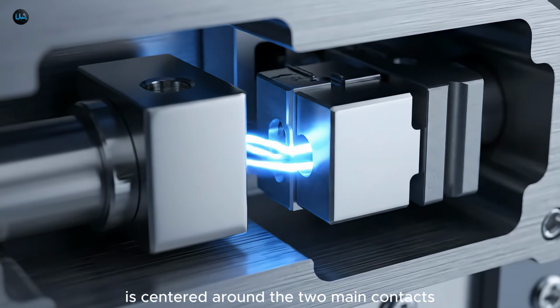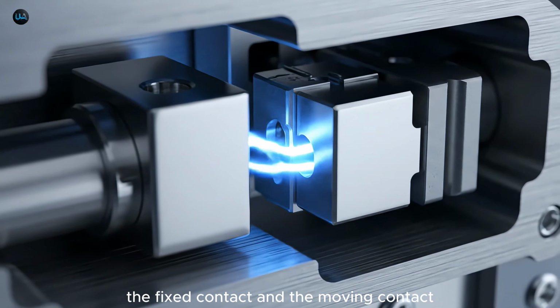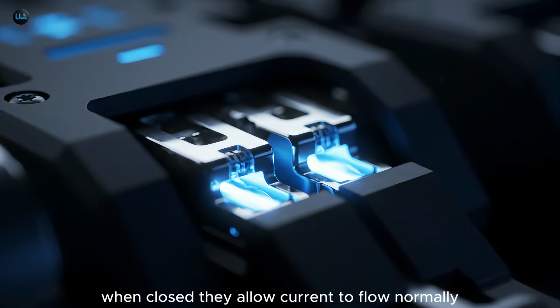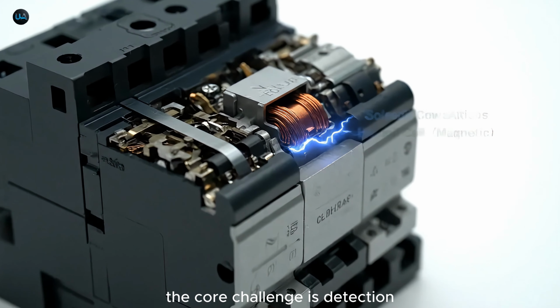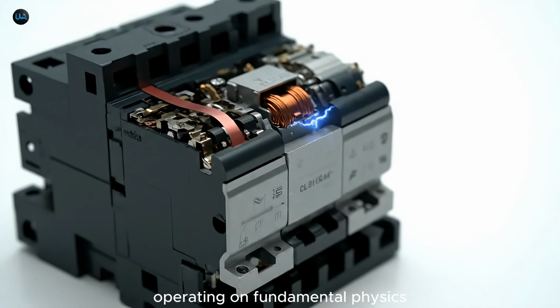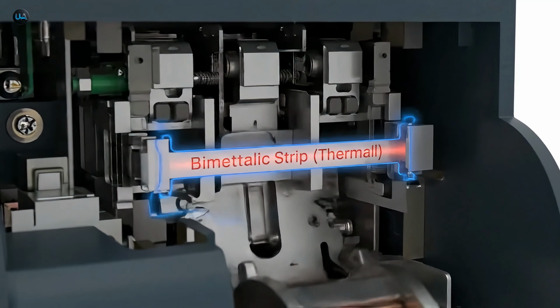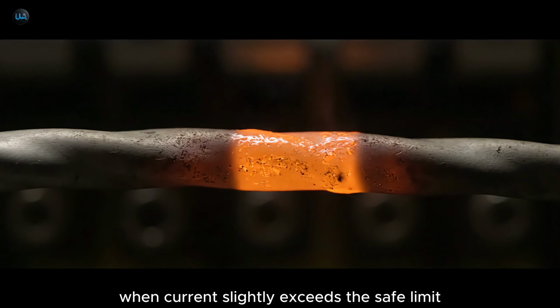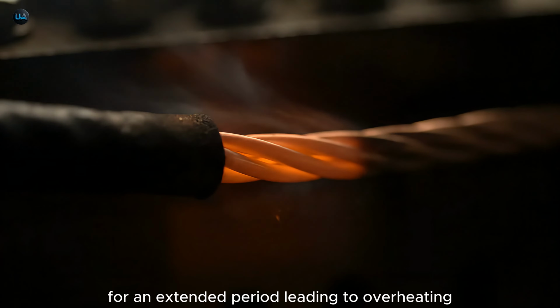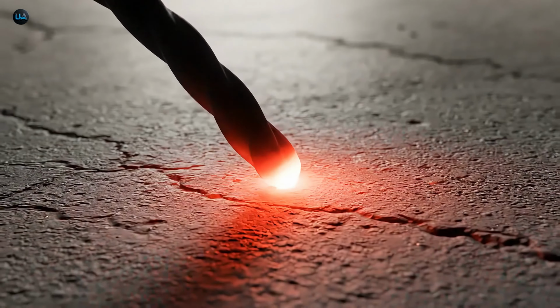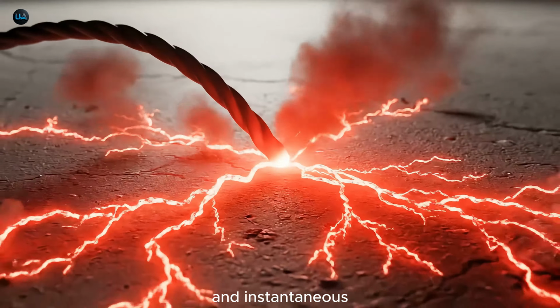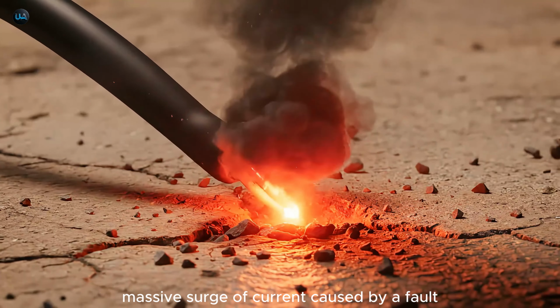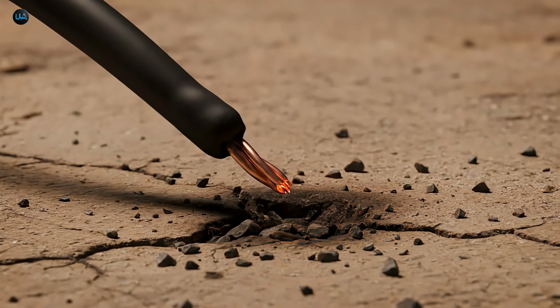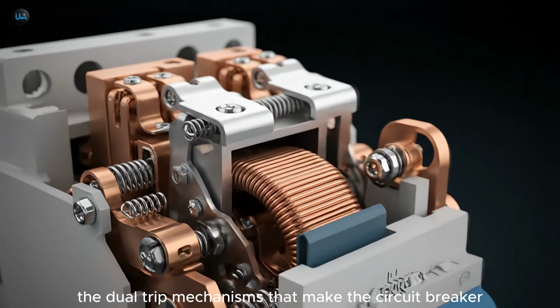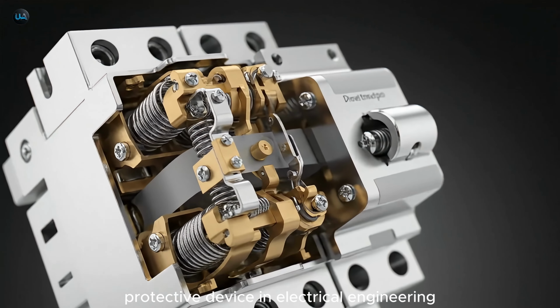The entire mechanism is centered around the two main contacts, the fixed contact and the moving contact. When closed, they allow current to flow normally. The core challenge is detection. The breaker uses two distinct sensors, operating on fundamental physics, to monitor the current passing through. The first defense is against overload, when current slightly exceeds the safe limit for an extended period, leading to overheating. The second defense is short circuit and instantaneous: a massive surge of current caused by a fault, which must be interrupted in milliseconds. Let's explore the dual trip mechanisms that make the circuit breaker the most reliable protective device in electrical engineering.